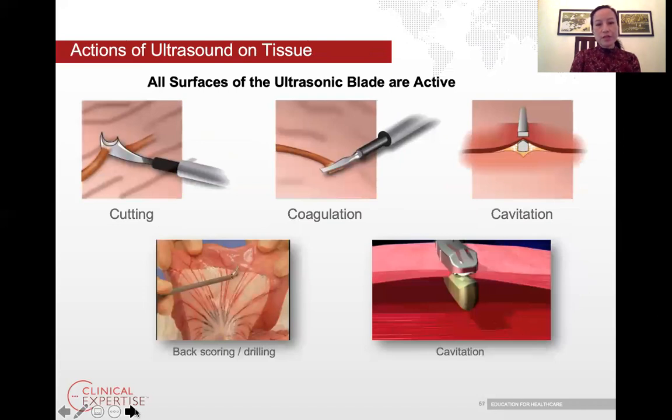Ultrasonic instruments enable a surgeon to cut and coagulate tissues simultaneously. Cutting with an ultrasonic instrument is entirely different from cutting with an electrosurgical instrument. With electrosurgery, cutting is achieved using a current. The current creates higher tissue temperatures in a shorter period of time, leading to rapid expansion of intracellular fluids and cell explosion or vaporization. With an ultrasonic instrument, cutting is achieved with direct contact of the blade to the tissues, comparable to cutting with a conventional cold steel scalpel.